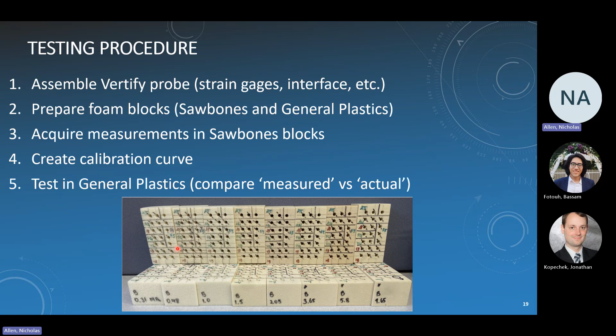But we acquired measurements from our Sawbones blocks. From that, because we want a consistent type of foam that was manufactured, we then created a calibration curve for each one of the probes. Then we tested against the General Plastics, which was a different value, because we didn't want to test the value we calibrated at, because it makes things really, really easy for us. So we actually wanted to have a value that was between these calibrations. So I'll show you a calibration curve in a moment. But then we would test it in the General Plastics and compare our measured value, based on the prior calibration, to the actual to see where we're at.